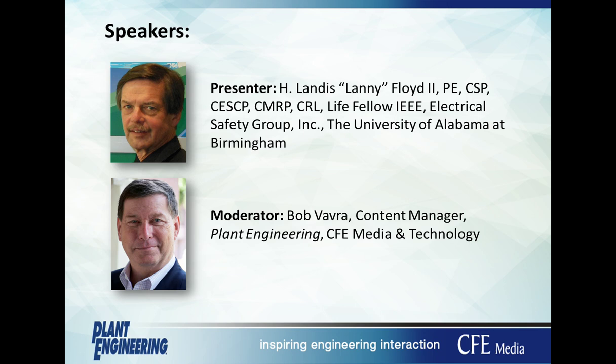I'm assuming we're talking about 480 volt Delta secondary that may be ungrounded. There are opportunities—let me back up. Ungrounded Delta systems were common back through the 1950s. It was thought that would not only be safer but also improve the reliability of operations. Experience with ungrounded systems found they weren't as reliable as we perhaps thought, and created some other operating difficulties. I won't go into the details, but grounded Delta and grounded Y, center grounded Y, became the standard in the 70s, 80s, and through today.